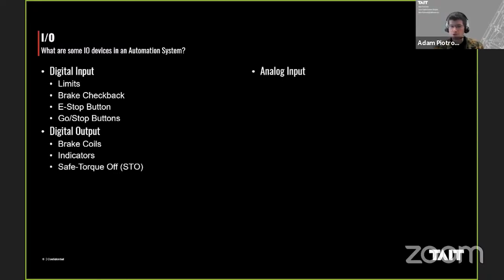So jumping over to analog inputs, things like load cell, the position feedback in terms of the encoder, and any kind of jog joysticks. A load cell can be used on a winch to confirm the load you're picking up, kind of used as a scale, but also for safety functions and performer flying, ensuring that the machine stays within its designed limits. So if it can only lift 5,000 pounds, we don't try to pick something up heavier than 5,000 pounds. You don't really have a way of doing that if you don't put a load cell online.